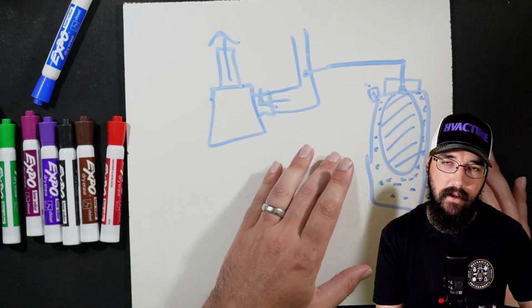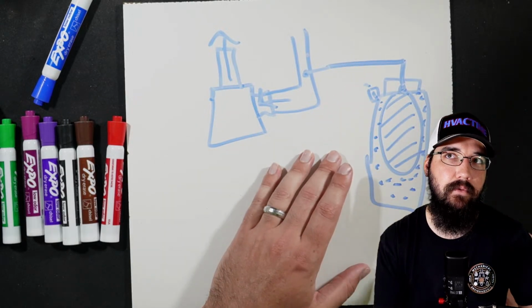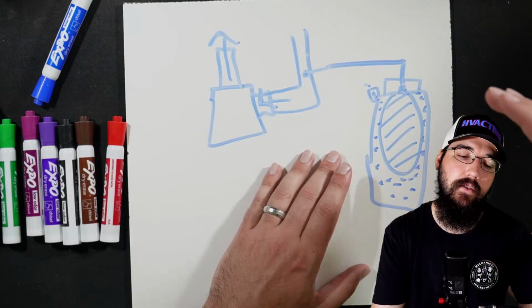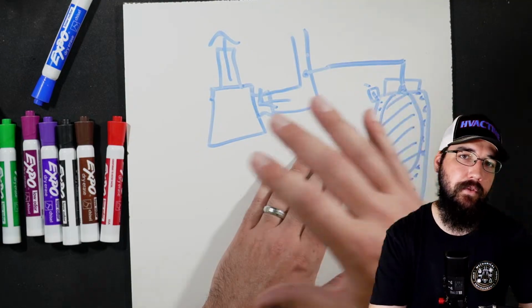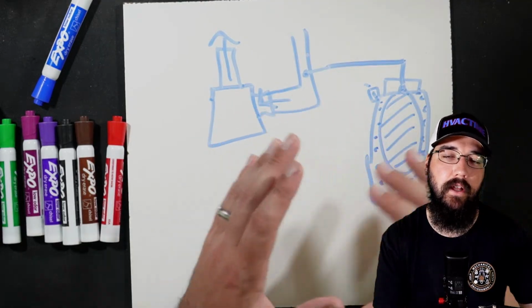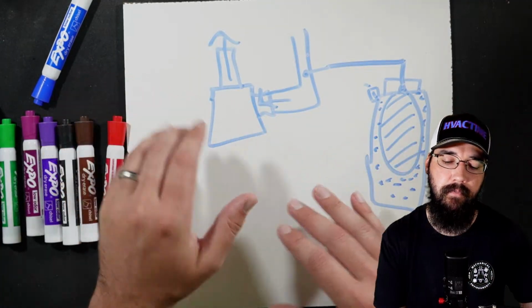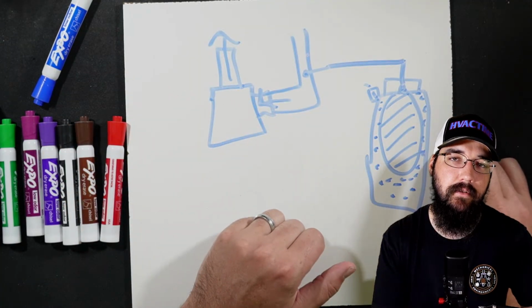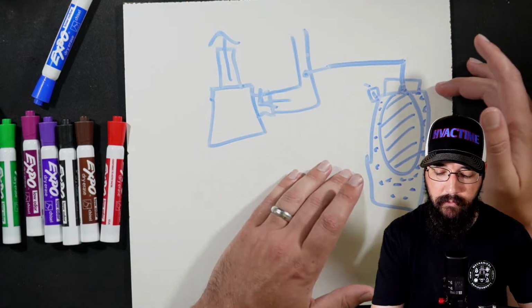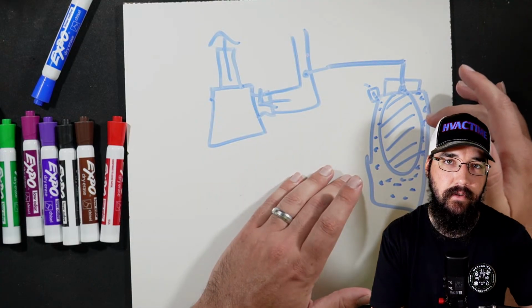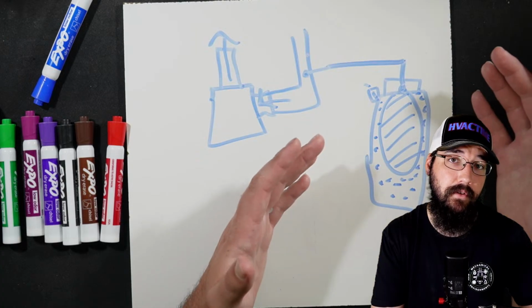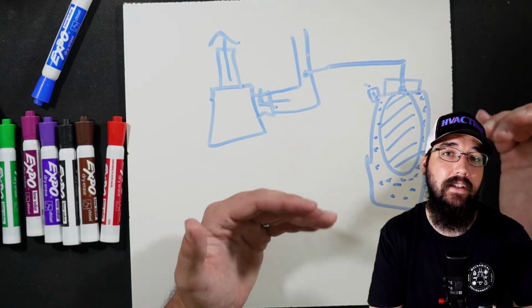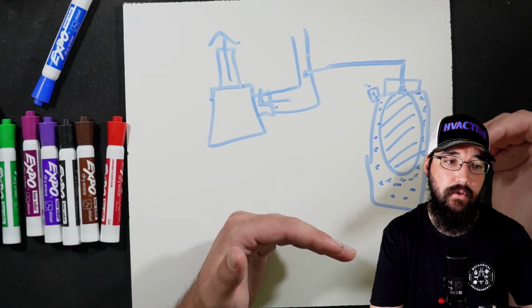I have found that a lot of these don't get field calibrated. So they'll get put by the pumps, but the pumps are down several stories below, so they're not at the top of the loop, they're more towards the bottom. But they did not change the calibration on this.